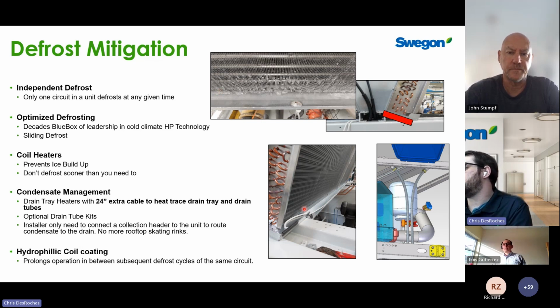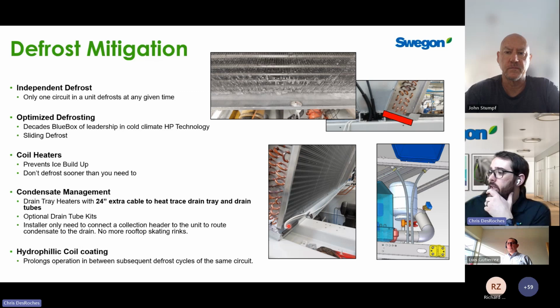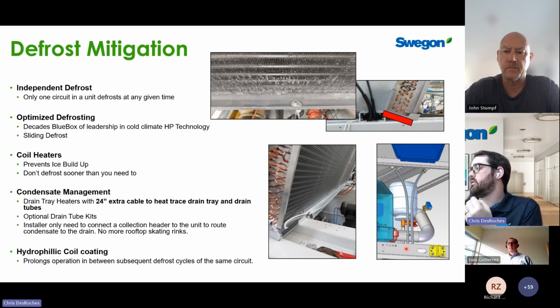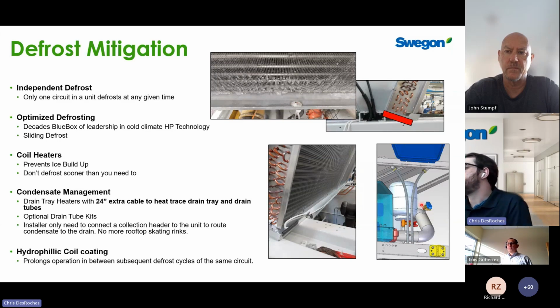On the drain tray itself, we want to make sure that we have continuous drainage. So we have drain tray heaters going across the coils. And we actually provide these heaters with about 24 to 30 inches of additional cable length so that you can fit it through the drain outlet and feed it down the condensate drainage tubes. So now in the field for the contractor, as part of your designs, you need to put in a condensate collection header, collect the condensate and route that to a drain. So it's going to prevent a skating rink from basically building up directly below the units.